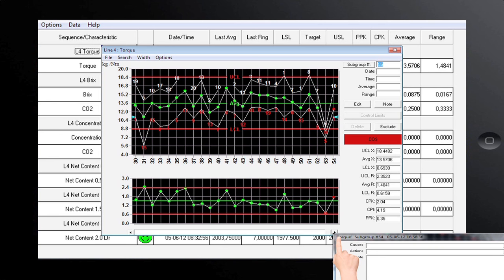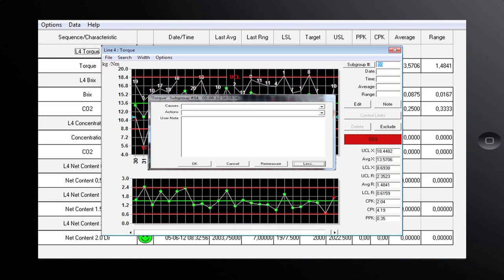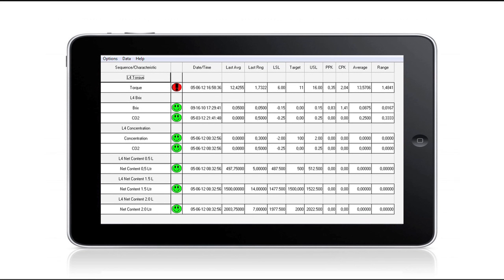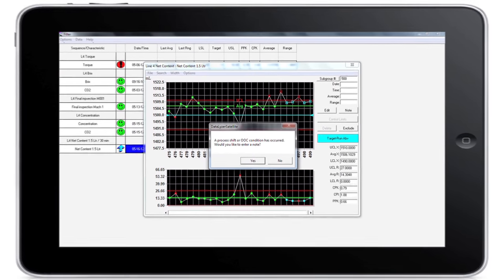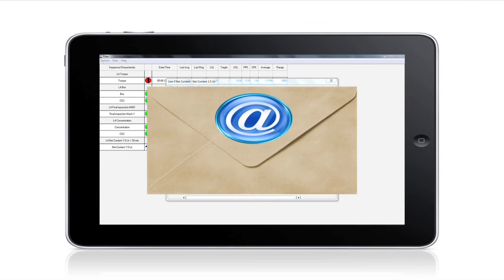If you look closely, you will see that the chart is configured differently from the previous examples. Because we measure a lot of positions, the operator is provided with extra information to help find the cause of the problem quickly. In this example, the operator enters a free form note and the system returns to the status screen. Measurements can be recorded in different ways — carbon dioxide, brix, and net content can be measured manually or fully automatically. With automatic measurements, Datalyzer can extract the values from a PLC or from a database and present them to the operator. The example process shows a run above target, and the system can be set up to send an email automatically when a problem is detected.